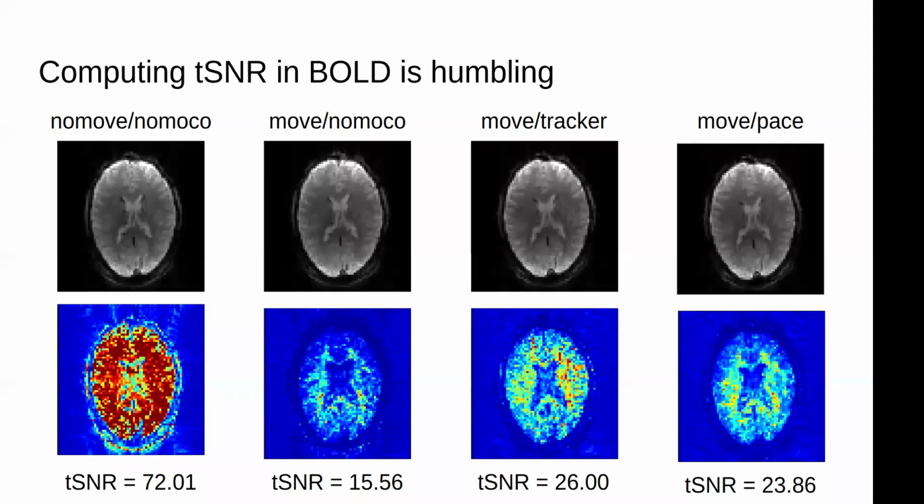If the participant moves during a BOLD EPI frame, then what's getting excited and read out is not what we intended, based on where the scanner thinks the head is. And there's no way to undo that, right? The only thing we can do is use that information to apply a correction to our next data point. So is that really what's driving this hit, because there's no undoing what's in the past, and that's still going to impact our calculation?